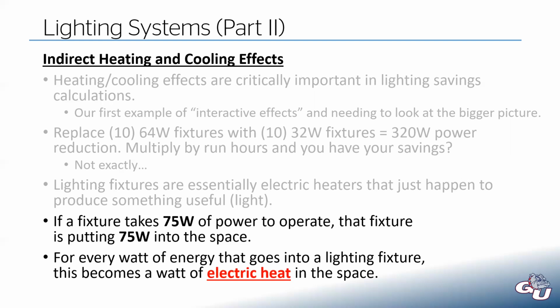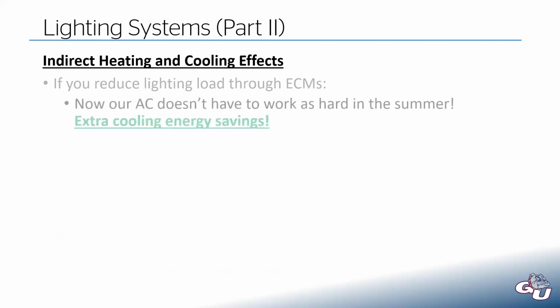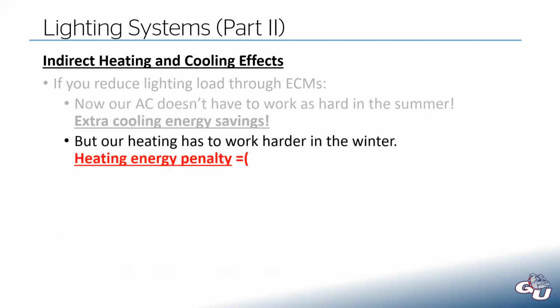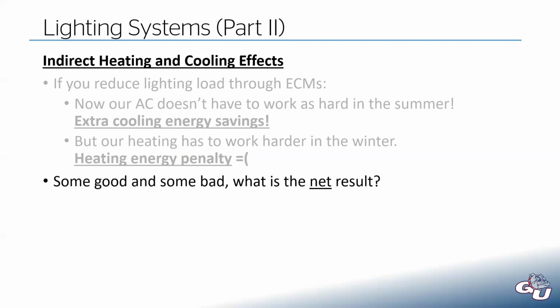And that's going to impact our heating and cooling. If we reduce our lighting load through some combination of energy conservation measures, now our air conditioner doesn't have to work as hard, so we get some bonus cooling energy savings on top of the lighting savings we've already calculated. But the heating system now has to work harder in the winter, so you actually pay a penalty for that reduced lighting output in the winter months. We have some good and some bad — what's the bottom line, what's the net result?